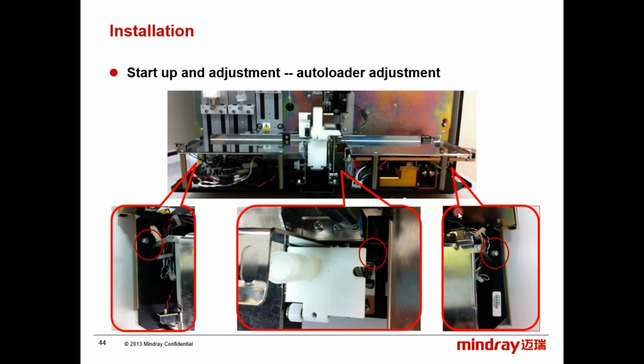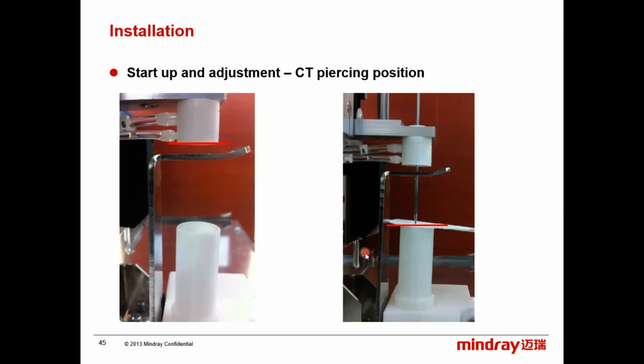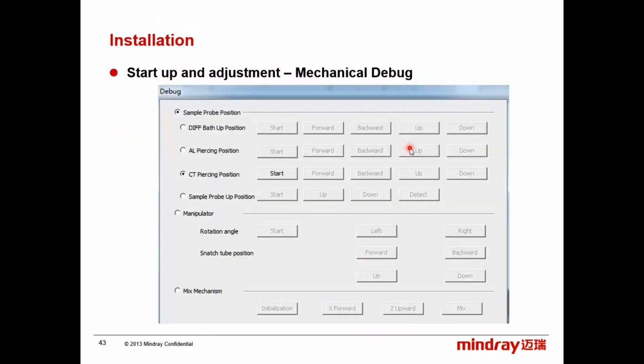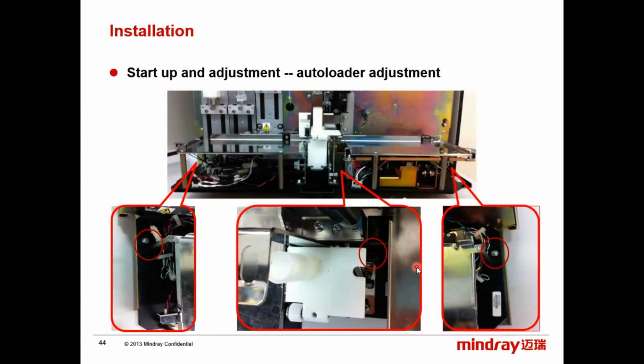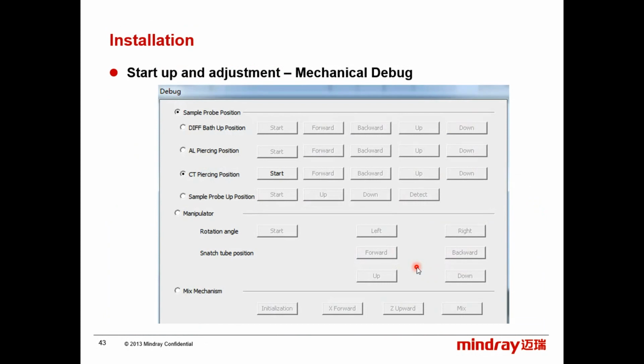Okay, so this is for the autoloader adjustment. It is mechanical adjustment. This is the closed tube piercing position. It needs to be perfectly in the center. And here, as you see, why we need these mechanical adjustments, like manual adjustment with the screwdrivers, is because here we can only move our probe in the Y and Z direction, but the X direction is not available. All right.